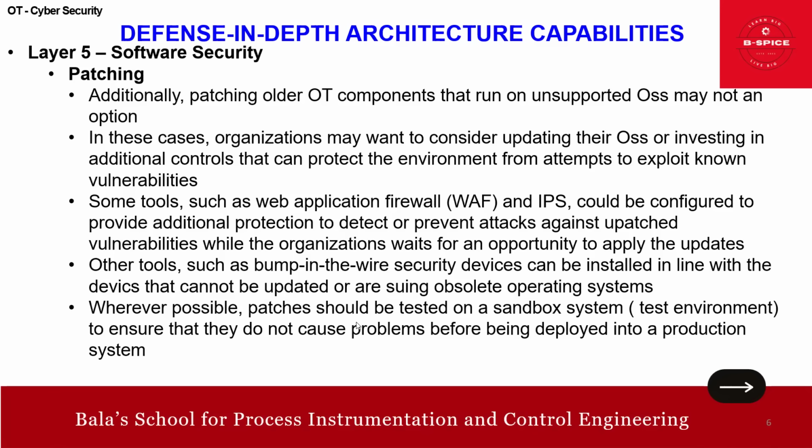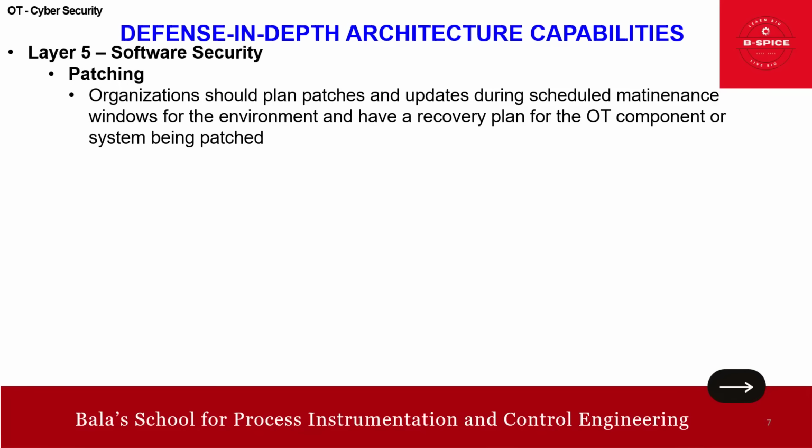Wherever possible, patches should be tested on a sandbox. What is a sandbox? It's a test environment to ensure that patches do not cause problems before being deployed into the production system. So that's about the patching. To continue more on patching, organizations should plan patches and updates during scheduled maintenance windows for the environment and have a recovery plan for the OT component or the system being patched.